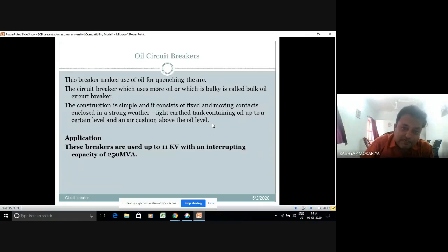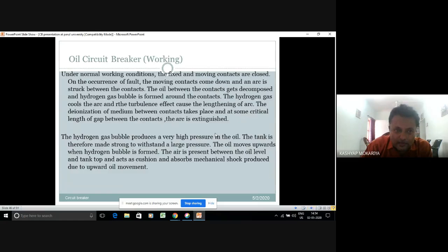The construction is simple and consists of fixed and moving contacts enclosed in a strong weather-tight earthed tank containing oil up to a certain level, with an air cushion above the level. So this is basically the OCB. Under normal working condition, the fixed and moving contacts are closed. On the occurrence of a fault, the moving contacts come down and an arc is struck. The oil between the contacts gets decomposed and hydrogen gas bubbles form. Those who have studied the Buchholz principle can see this. The hydrogen gas bubbles form around the contacts, the hydrogen gas cools the arc, and the turbulence causes lengthening of the arc and de-ionization of the medium between the contacts. At some critical length of gap between the contacts, the arc is extinguished.